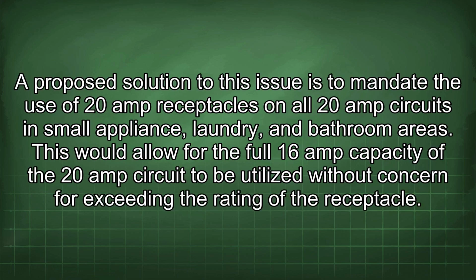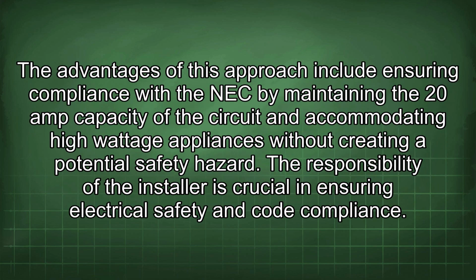A proposed solution to this issue is to mandate the use of 20-amp receptacles on all 20-amp circuits in small appliance, laundry, and bathroom areas. This would allow for the full 16-amp capacity of the 20-amp circuit to be utilized without concern for exceeding the rating of the receptacle. The advantages of this approach include ensuring compliance with the NEC by maintaining the 20-amp capacity of the circuit and accommodating high-wattage appliances without creating a potential safety hazard.